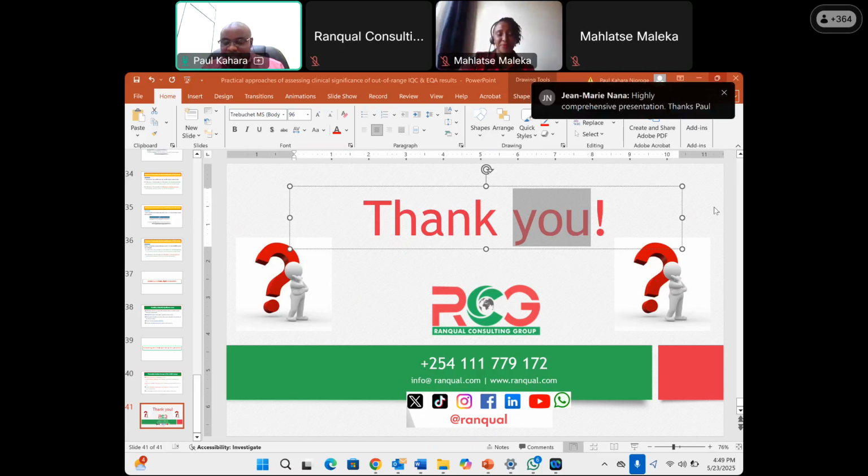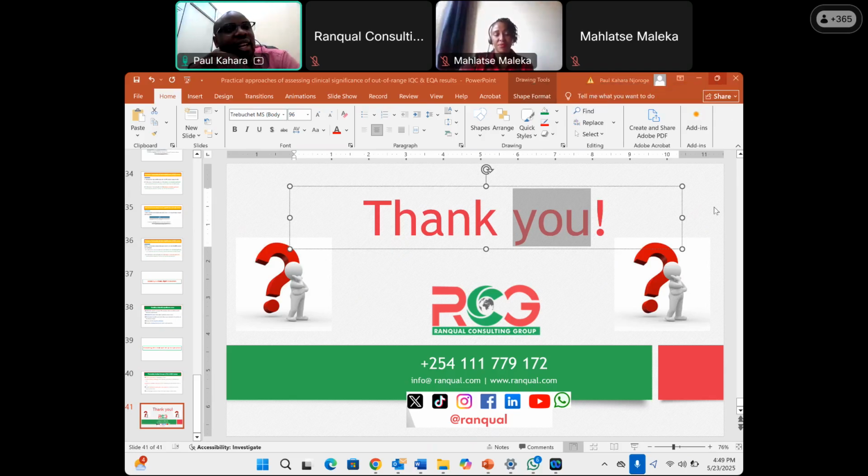Okay, let me start with that last one. I know, like for hematology, these CBC analyzers, they will tell you that the IQC has to be used within, let's say, 14 days. So after 14 days, you cannot go ahead and use the IQC material. So first of all, it's good that we adhere to the manufacturer's instructions, the guidance. When they tell you that after 14 days, we cannot assure you that the results we are going to get are okay. So even if it is passing, please know that it is passing by God's grace. If the equipment has a little other problem, you may not be able to get that passing.